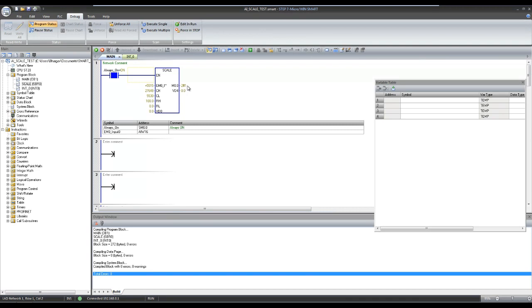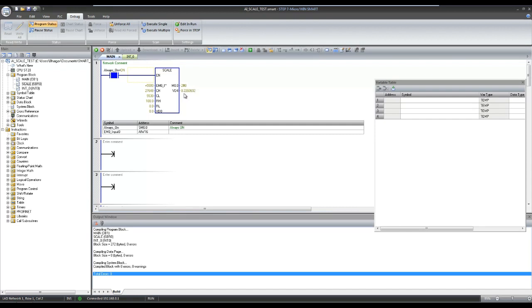Now I am changing input to 8 milliamps. That is 25% of 4 to 20 milliamps scale. And the output is around 25.